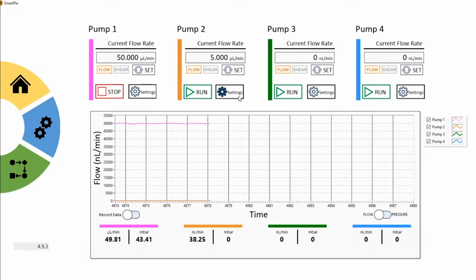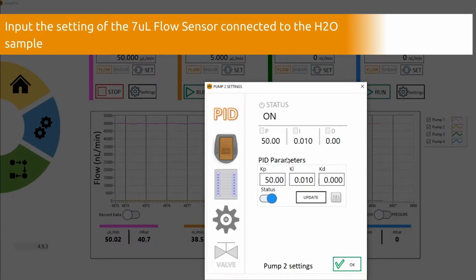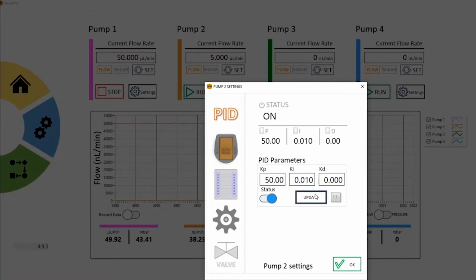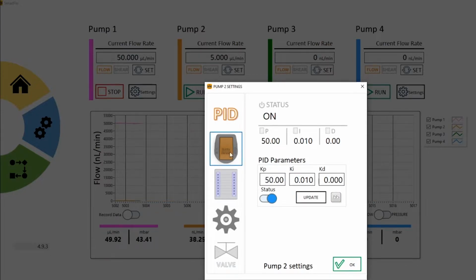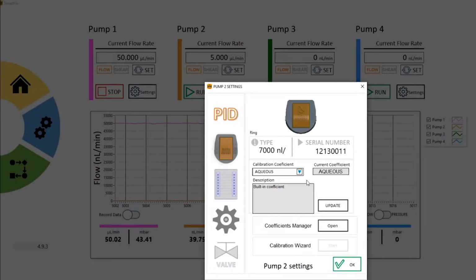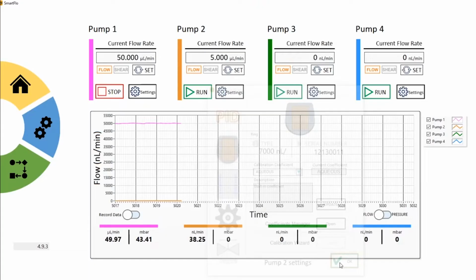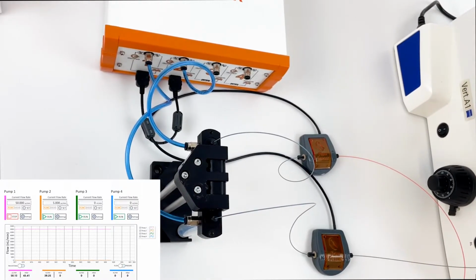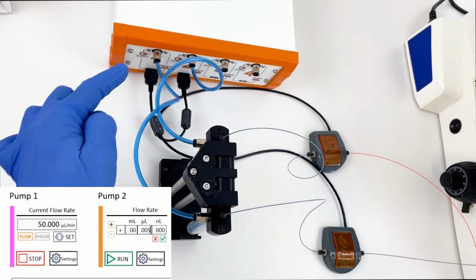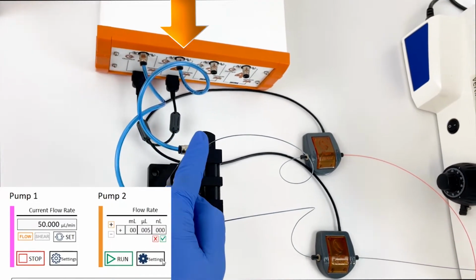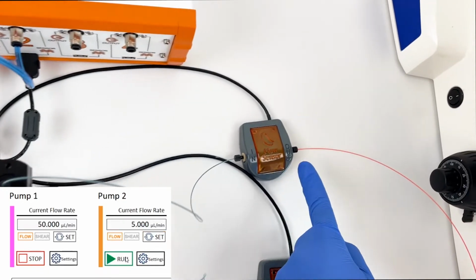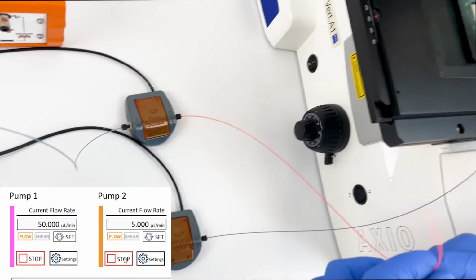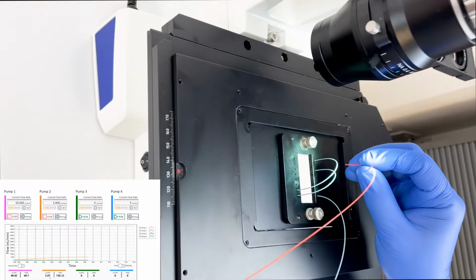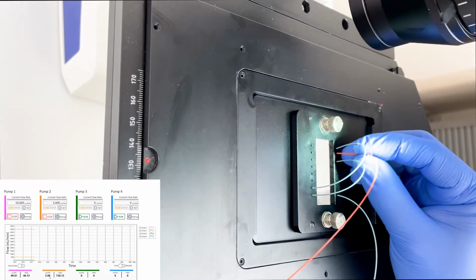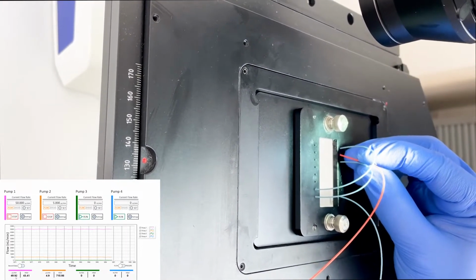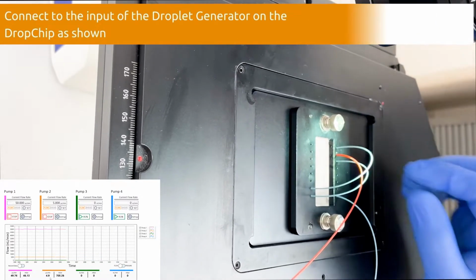Before starting the flow rate of the aqueous phase, first input the settings of the 7 microliter flow sensor connected to the H2O sample. To connect the aqueous phase, H2O in this setup, to the droplet generator on the drop chip, first start the flow rate of the aqueous phase, channel 2 of the 4U pump, at 5 microliters per minute. This primes the red PEEK tubing from the aqueous H2O sample tube. Once you see the droplets emerging at the output of the red tubing from the 7 microliter flow sensor, connect to the input of the droplet generator on the drop chip.